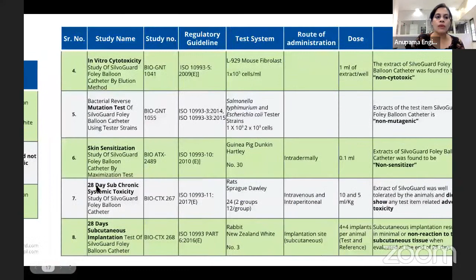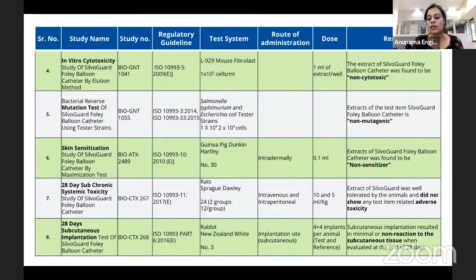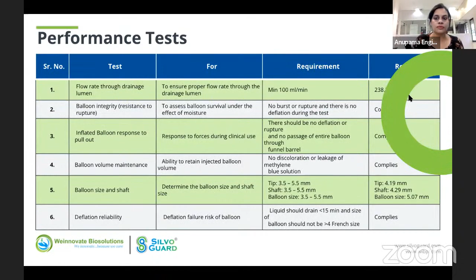So all the results suggested that SilvoGuard catheters are perfectly biocompatible in nature. We also carried out certain cytotoxicity tests and certain mutation tests, and we found these catheters were absolutely non-toxic and did not have any kind of mutagenic effect on the bacteria. So this indicated the biocompatibility and the non-toxicity of the SilvoGuard catheters. Moving ahead, we checked whether this catheter is functioning the way it is supposed to. There are Foley balloon catheter performance tests, and any Foley balloon catheter has to perform these tests to comply as a good catheter. So we did all the 6 tests which are necessary for the performance of any Foley balloon catheter, and in all the 6 tests we found that the SilvoGuard catheter complied with all the performance parameters for a Foley balloon catheter.